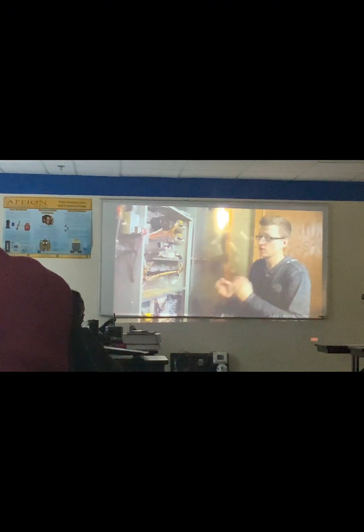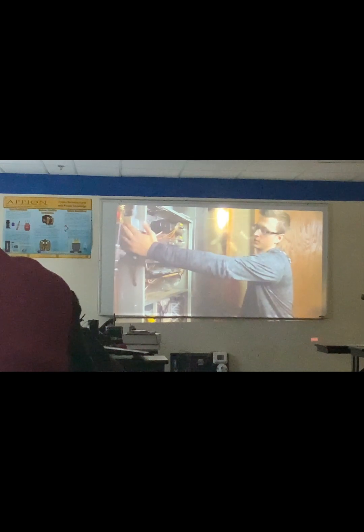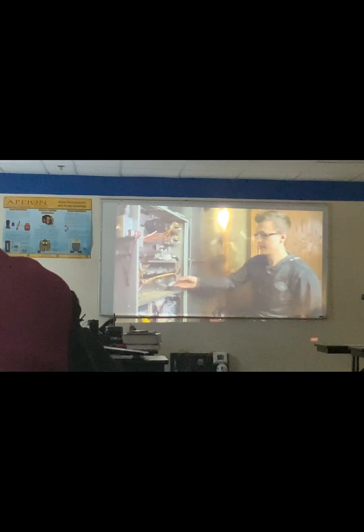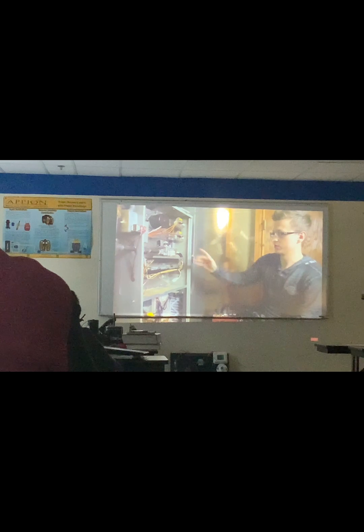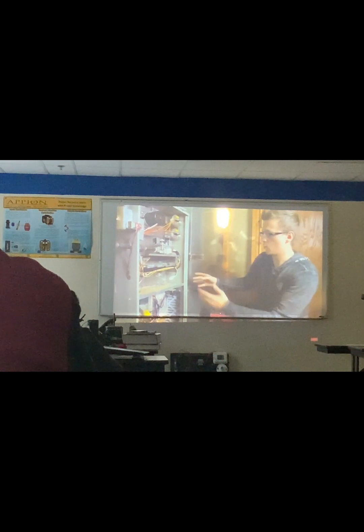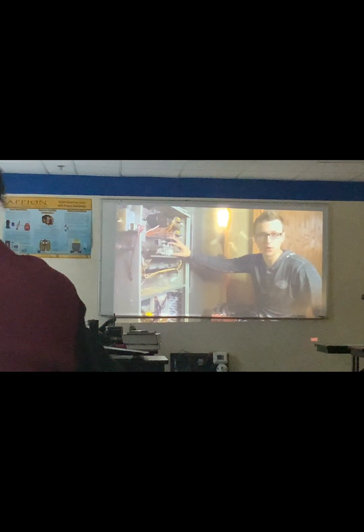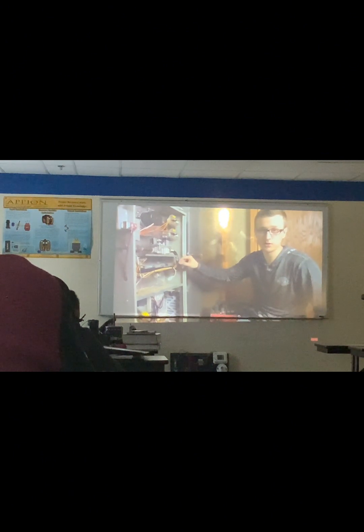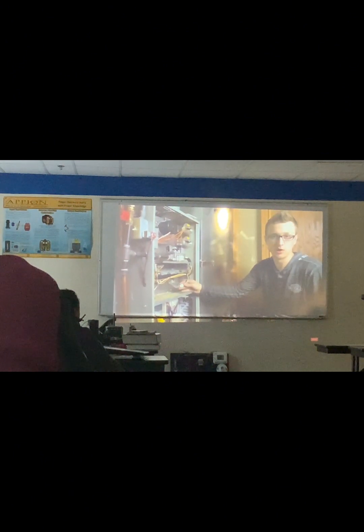Usually you'll have a plug like this, a little Molex plug that you can unplug. What that will look like is the customer says the furnace turns on, it seems to start working, but it never actually lights. So I come down to the basement, I turn the furnace switch off, turn it back on, and see what it does. So you'll see the inducer motor come on. After a while, generally you will hear the gas valve open and a little bit of gas will come out, but the igniter was never glowing.